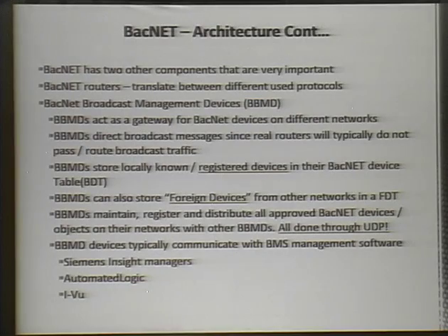I said 2 components that I really want to focus in on just a little bit. I talked about the BACnet gateway device, or these routers or broadcasting equipment. They store 2 things that are kind of important for us. One is called the BDT, or BACnet Device Table. What that table is basically a listing of all the objects, valves, controls, HVAC sensors, temperature readings, that kind of thing, that are understood and controlled or are providing that information and sending it up to a building management or SCADA system.